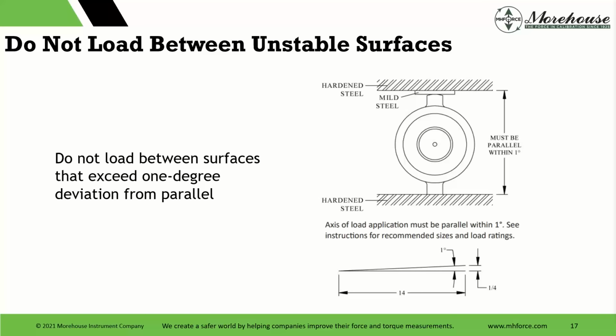Something else. Do not load between unstable surfaces. Under load, the instrument could be ejected from the machine with tremendous force. Never use a setup where there are two spherical surfaces opposing another without making the appropriate adapters to contain the instrument. And now we have do not load between surfaces that exceed 1 degree deviation from parallel. That's really what we're saying here, that this is a dangerous situation.